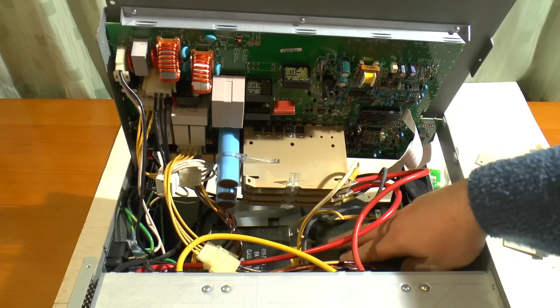There are 2 great big transformers at the bottom, and the primaries of these are wired in series. So the white wire goes down to there, the black wire goes through and spliced into the white wire, and then comes back up to here onto 2 of these heat sinks. The other 2 heat sinks, 2 of them go to battery terminals, although interestingly this one goes to the external battery terminal, and this one goes to the internal. So you've got the internal batteries are between this black wire here, the yellow, and then the red wire here.